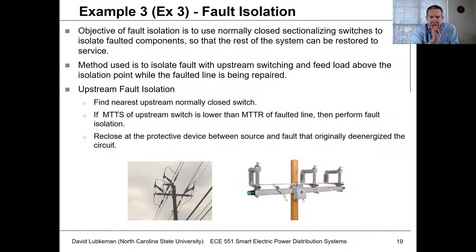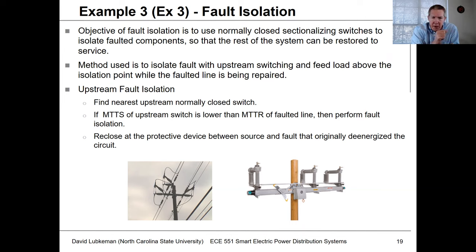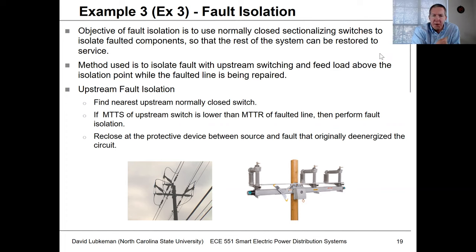We'll take a look at another type of scenario involving switches. These could be manual switches, motorized switches we can control via SCADA, or a recloser could actually be used as a switch. What this scenario involves is if we have a faulted section, we're going to isolate that section so we can restore service to the rest of the circuit. These are normally closed switches that we could open as needed. We'll talk first about upstream switching and upstream isolation, and then the example after this will cover what happens when we have a downstream switch that gives us even more flexibility.